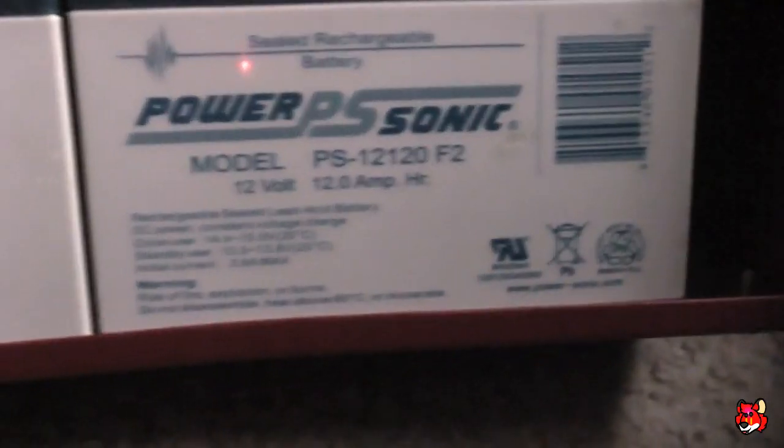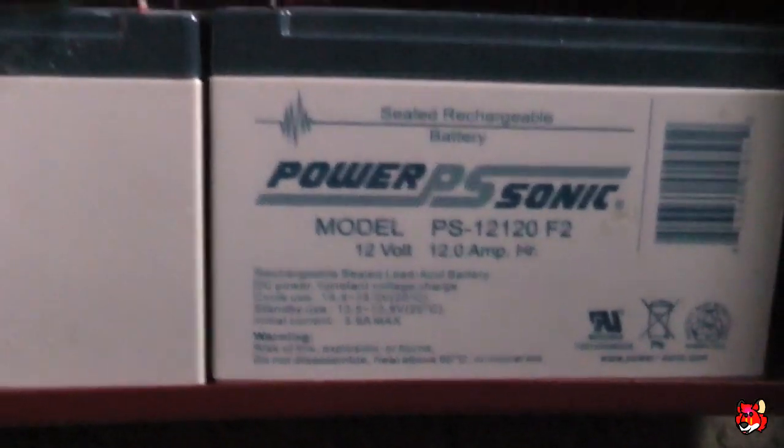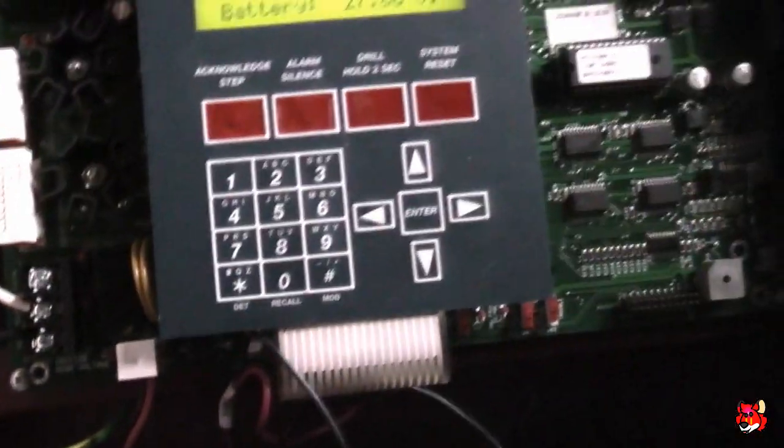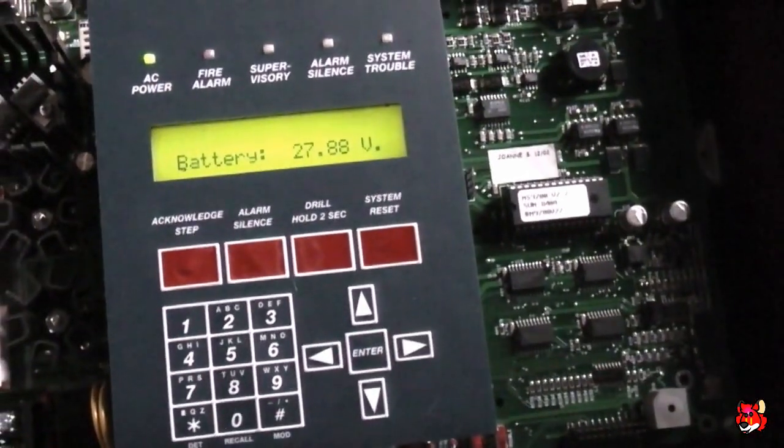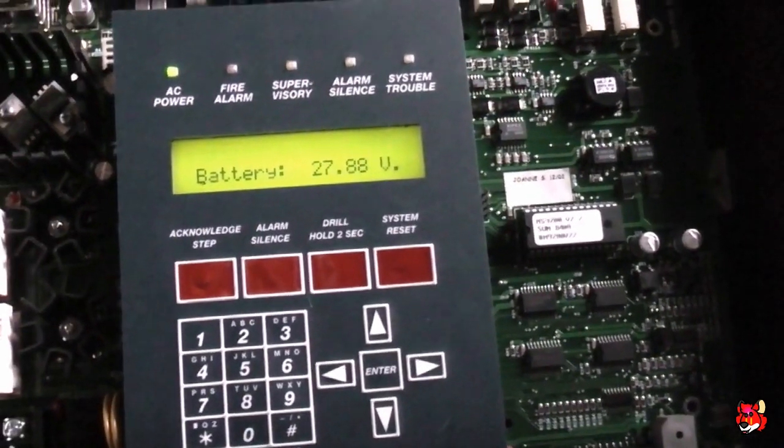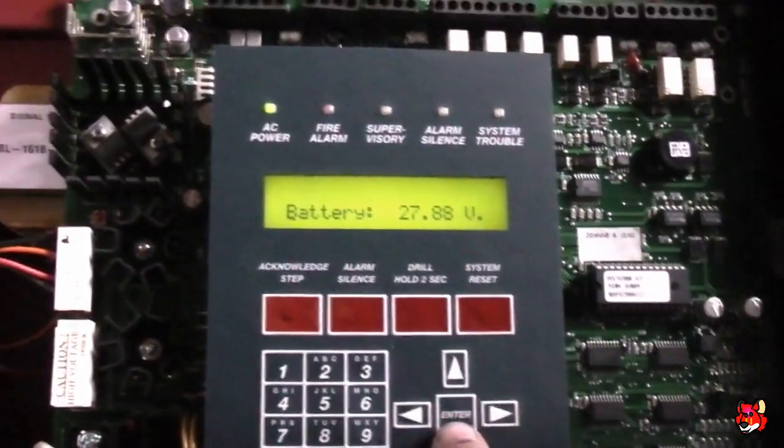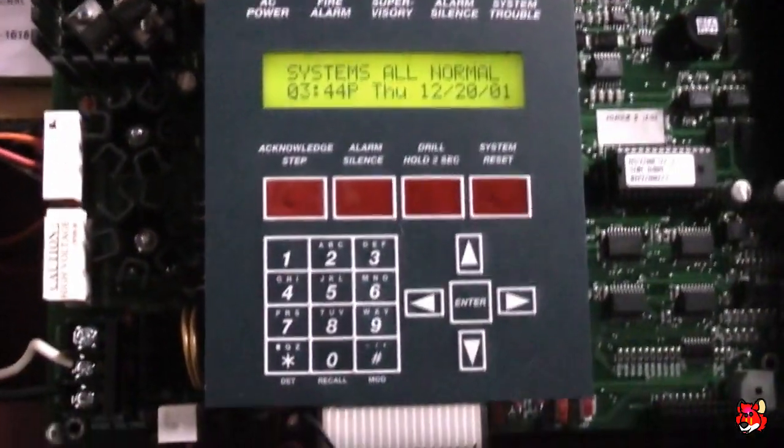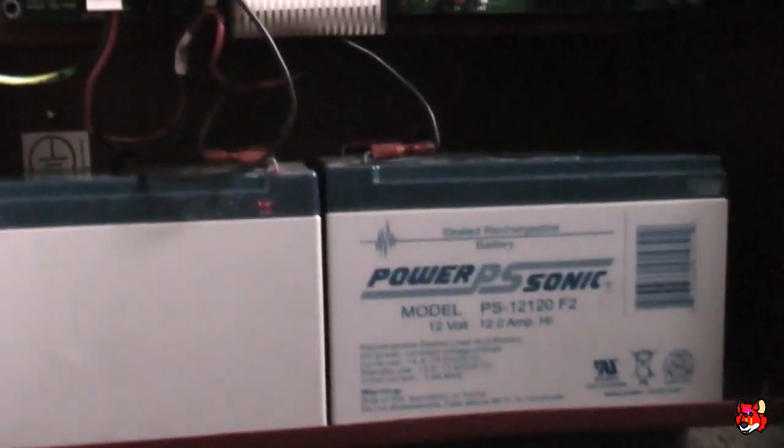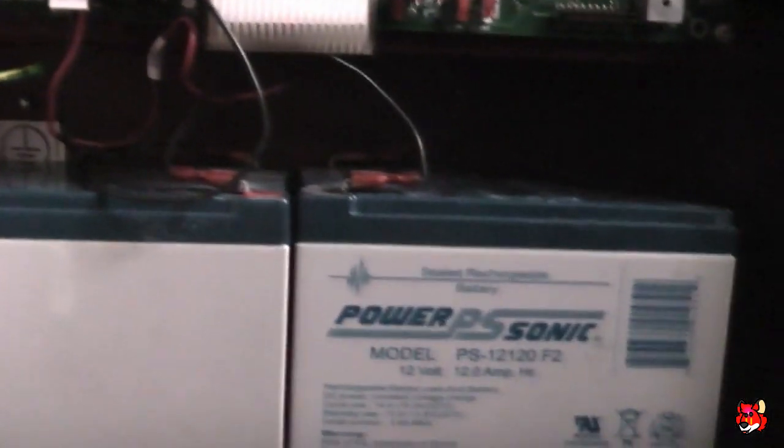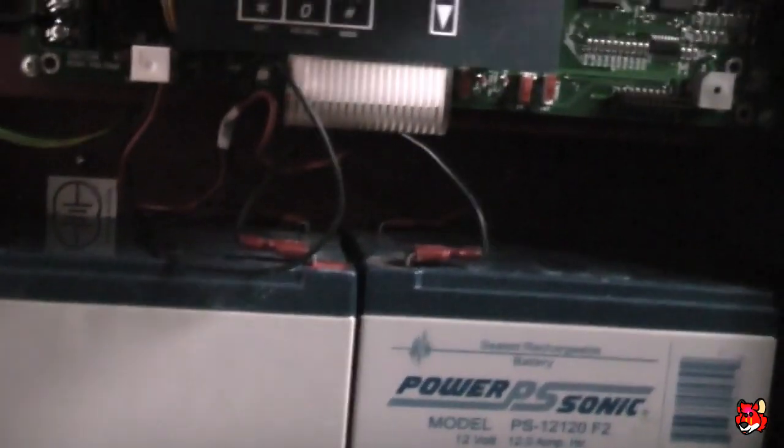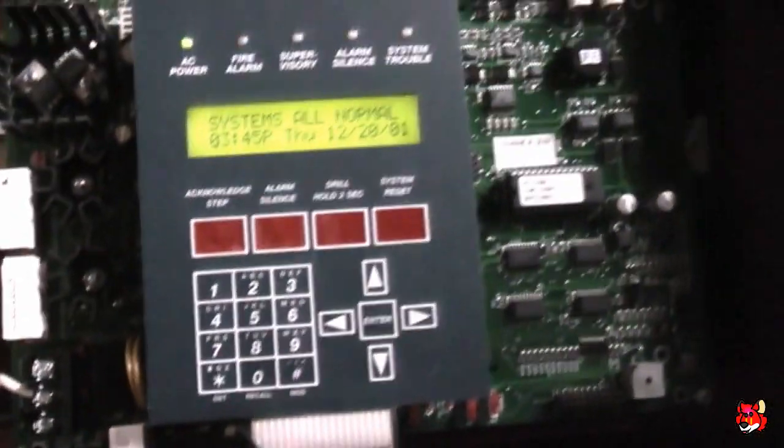And these batteries, as you can see, these are bigger batteries. And what I use in that, they are 12 amp hours. And these were the batteries that are actually original to it, and they actually have a good charge to them right now. 27.8 volts. And I have thought about putting these in that, but I'll probably just keep these around for demonstration systems. And since this panel won't be on all the time, I'll probably pop them in the NFW-50 so that way I can keep the NFW-50 on.